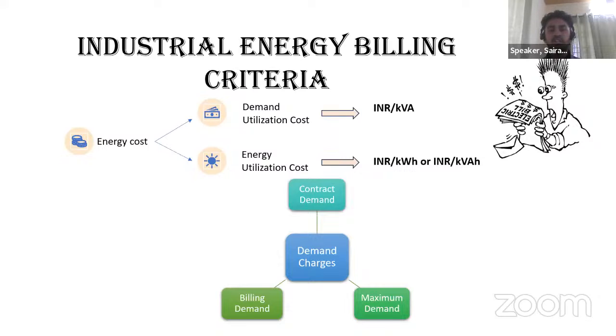Majorly, the energy cost is divided into two major categories: demand utilization cost and energy utilization cost. These two parameters will be billed separately in the energy bills from the grid. The demand utilization cost will be billed as per the kVA. They will be quoting an amount specifically for the demand that you are getting from the grid. And then the energy utilization cost is taken in two forms, like INR per kilowatt hour or INR per kVAH.